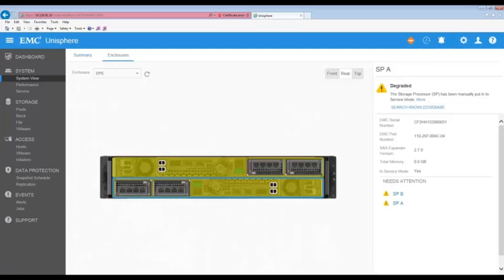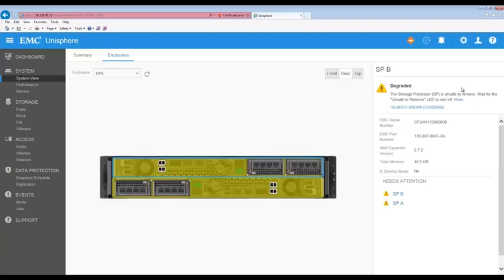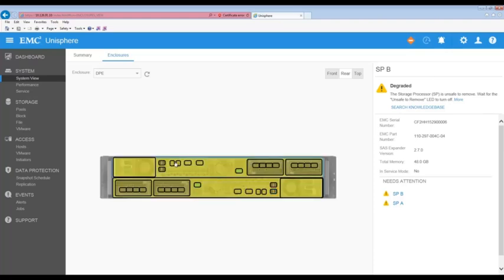Here we can see SPA and SPB are reporting errors. If we select SPA we can see that it is reporting that it is in service mode. If we click on SPB we can see that it is reporting an unsafe to remove condition.